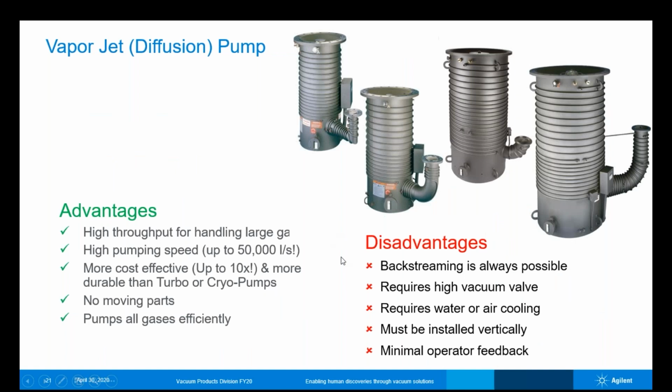We're going to talk about vapor jet or diffusion pumps. Personally, I prefer the name vapor jet, since the mechanism of pumping here used to be thought of as diffusion of gas molecules into a stream of pumping fluid. Now I think it's really considered that the pumping effect is happening through momentum transfer. In fact, one of my colleagues mentioned recently that Marsbed Hablanian, one of the godfathers of the vacuum business, was petitioning the American Vacuum Society to change the name from diffusion pumps to vapor jet pumps. So he certainly got my vote in that case.